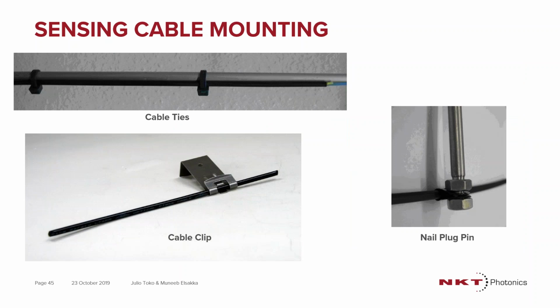Sensor cable mounting is fairly simple and flexible, as Giulio mentioned earlier. You can mount it with cable ties, nail plug pins, or a cable clip. Typically, as good design practice, you don't want too much sag in the cable. What most manufacturers in the fiber optic world suggest is a fixed point about every 3 feet. Of course, this varies from application to application, but the key is to have the cable near the point of interest for sensing.